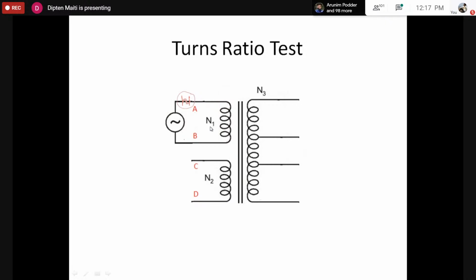So we would apply a voltage across capital AB. What is the rating of the voltage? What voltage can we apply? Of course, we can apply a lower voltage, but there's no point, since we have to use the transformer's actual rating. So we have to go by the nameplate. The nameplate says the rating is 110 to 220. So let's try with 110 volts on the small AB... capital AB.